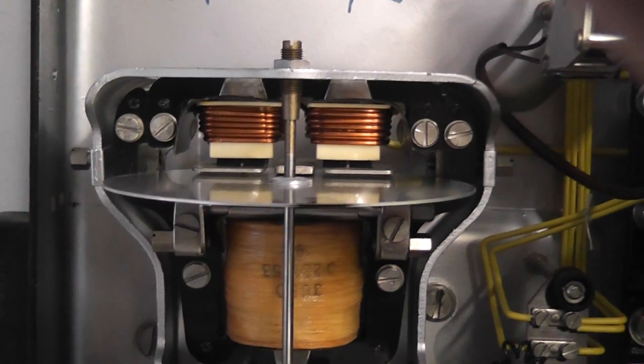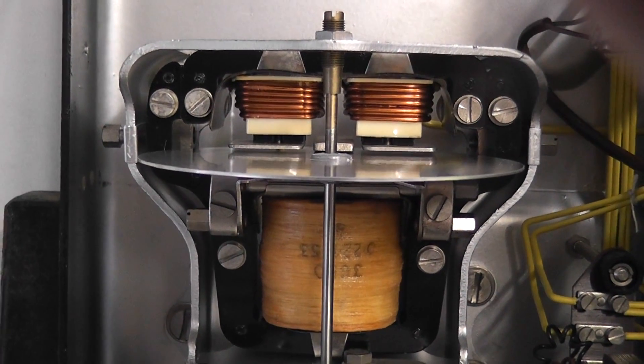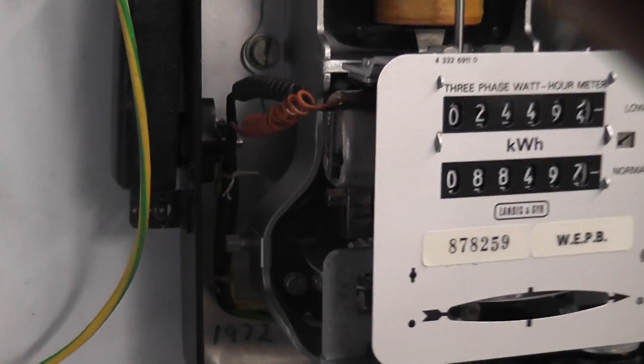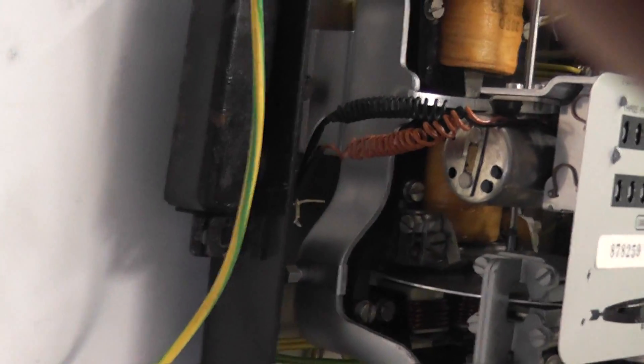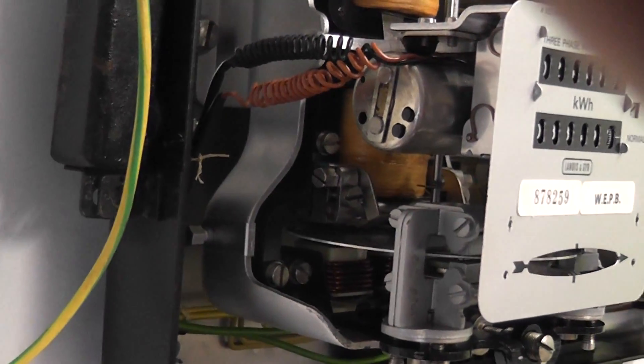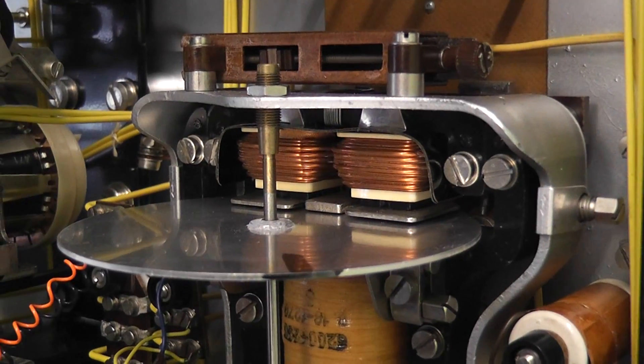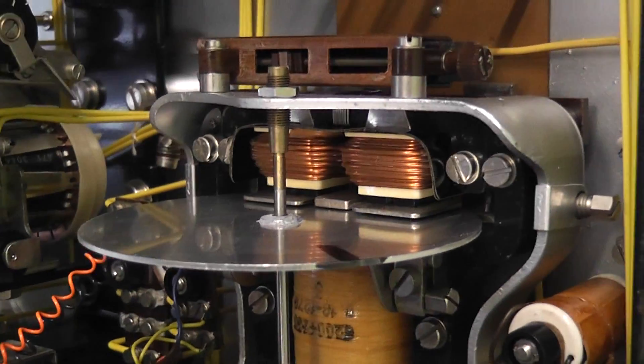The current coil are the copper windings above, while the yellow unit underneath is the potential coil. And behind the register, we got a similar setup duplicated with the potential coil above and the current coil underneath. The same is applied on the KVA register side.